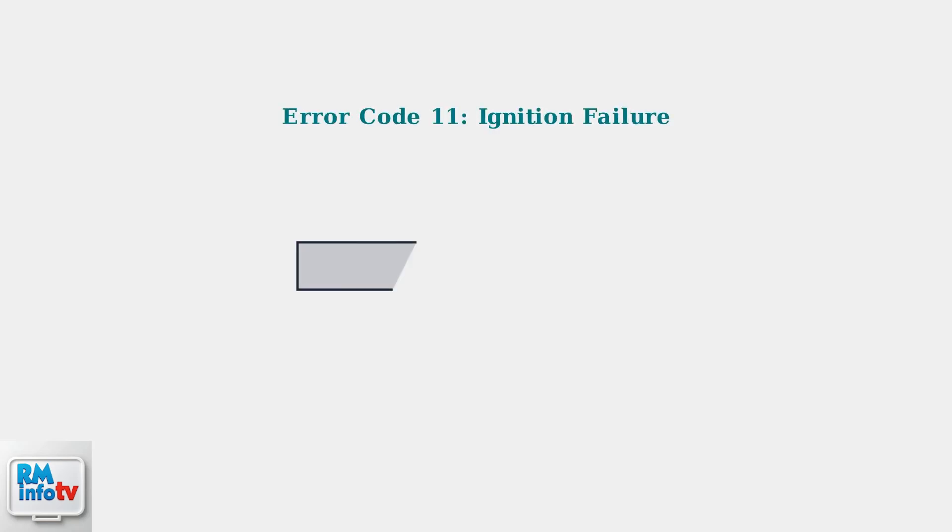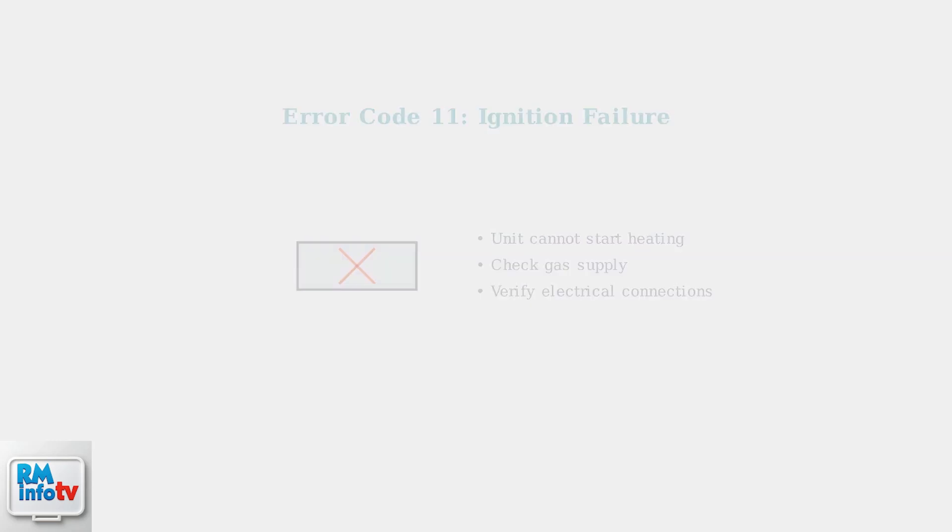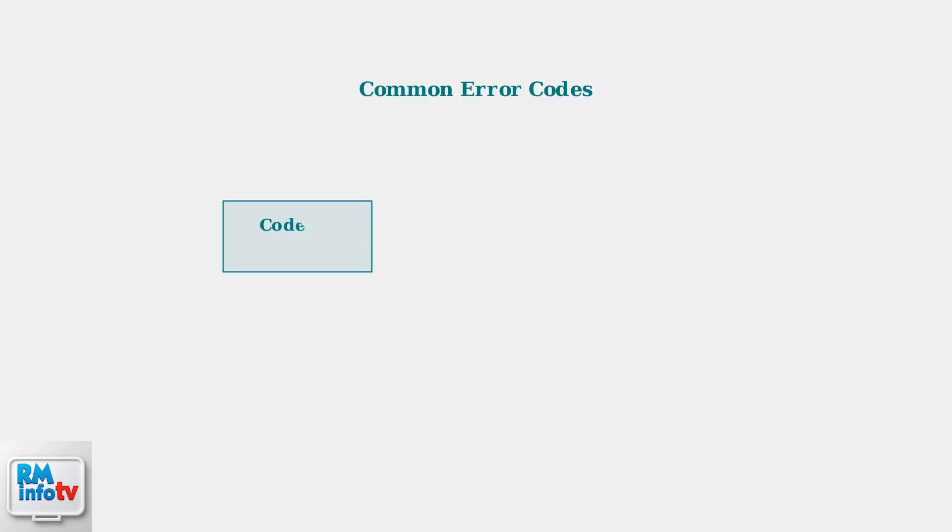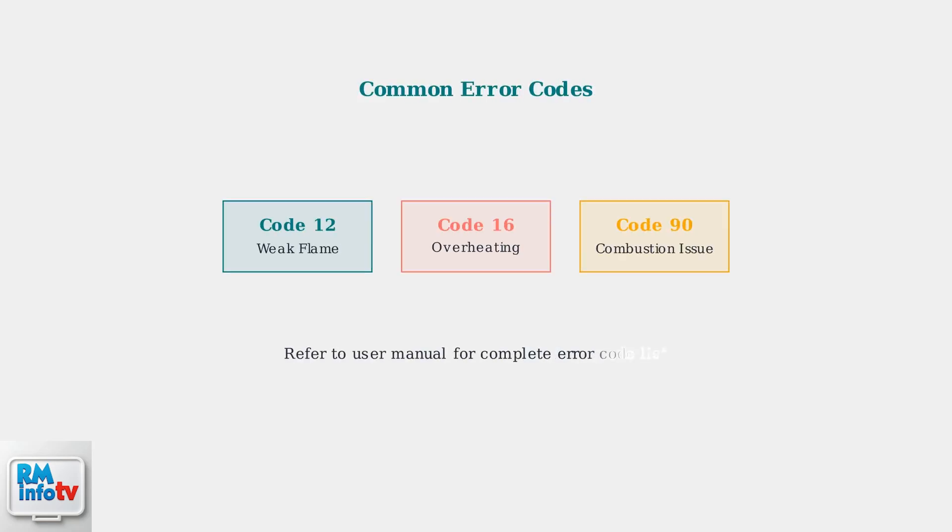The most common error code is 11, indicating ignition failure. This means the unit cannot start the heating process properly. Other frequent error codes include code 12 for weak flame, code 16 for overheating, and code 90 for combustion abnormality. Each requires specific troubleshooting steps.